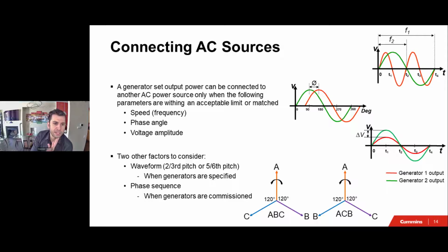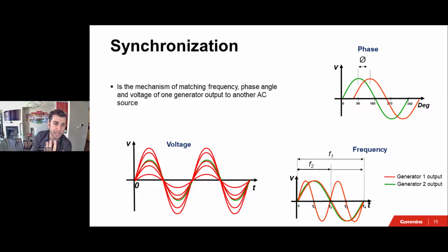We looked into those. So now every time we start the generator and want to close it into another AC source, we have to synchronize. Synchronizing is the mechanism by which we match phase, voltage, and frequency. We have to match these three elements, and later on I'll describe what controls are needed to handle synchronizing those three elements.